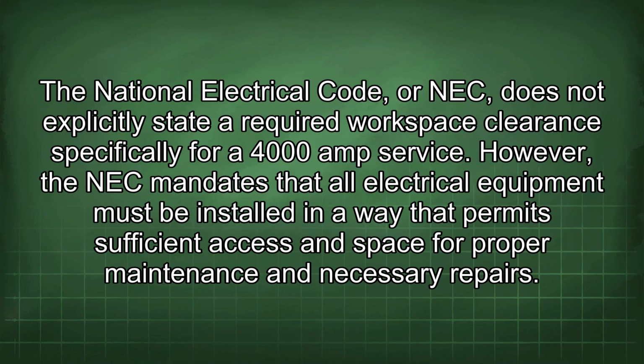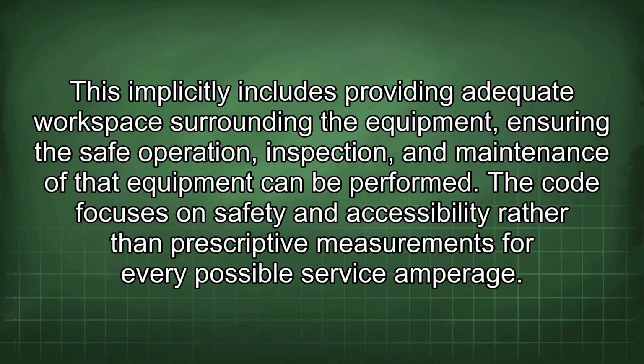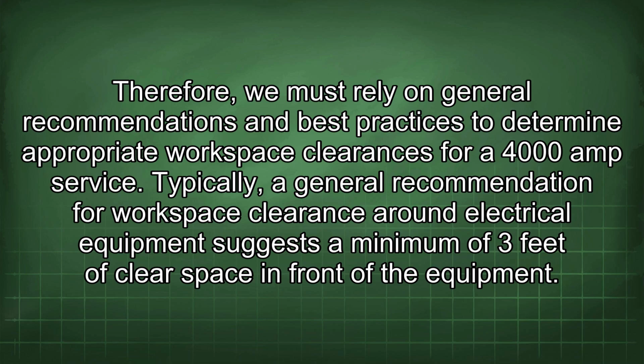The National Electrical Code, or NEC, does not explicitly state a required workspace clearance specifically for a 4000 amp service. However, the NEC mandates that all electrical equipment must be installed in a way that permits sufficient access and space for proper maintenance and necessary repairs. This implicitly includes providing adequate workspace surrounding the equipment, ensuring the safe operation, inspection, and maintenance of that equipment can be performed. The code focuses on safety and accessibility rather than prescriptive measurements for every possible service amperage. Therefore, we must rely on general recommendations and best practices to determine appropriate workspace clearances for a 4000 amp service.